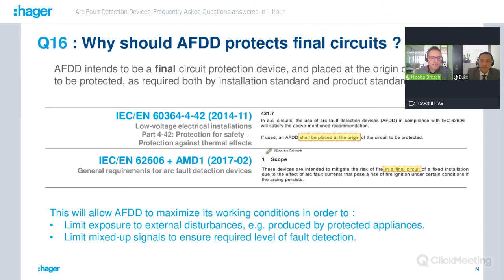So why should AFDDs protect final circuits? Because an AFDD is intended to be a final circuit protection device, placed at the origin of the circuit to be protected, as required both by the installation standard and the product standard. So here you have the exact chapter of both standards where this is mentioned. But I think you also want an explanation, because okay, it's written in the standard, but why?